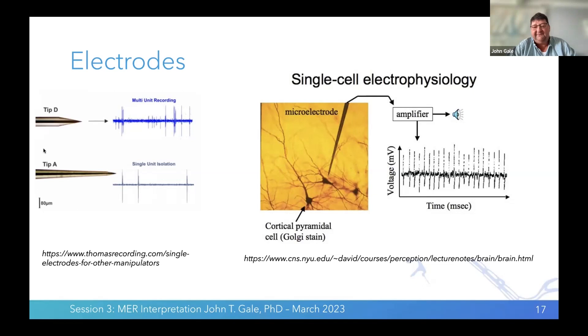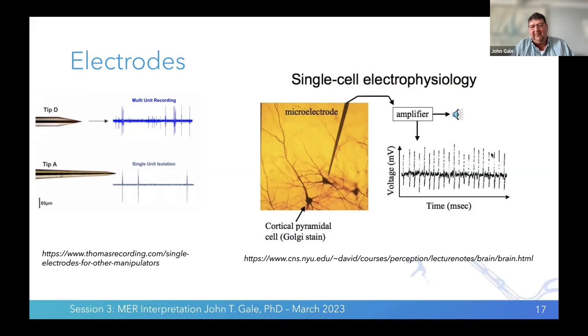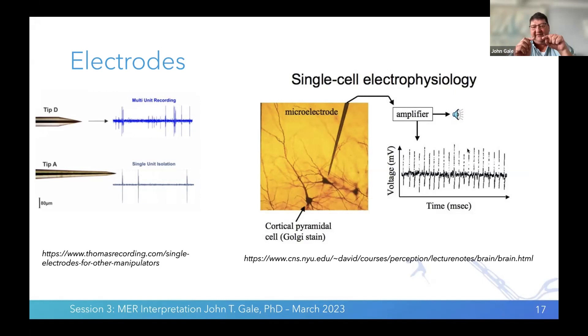In the lab, we have Faraday rooms for absolutely pristine recordings. Using our differential amplifier, you can see a neuron that appears to have a weird oscillating shape. This is what's known as a cardioballistic effect: a recording electrode near a neuron may have a nearby vessel — every time the heart beats, it pushes the neuron a little closer and then back. That small change in distance causes a small change in amplitude. The neuron's still firing the same exchange of ions, but your distance to the electrode is changing. The same thing can happen with breathing.